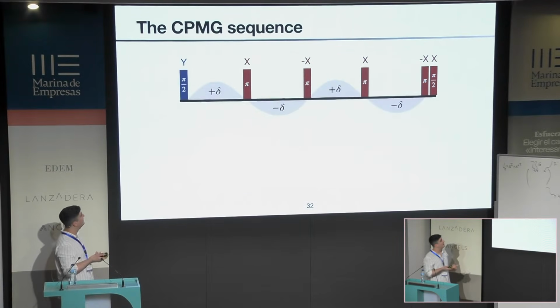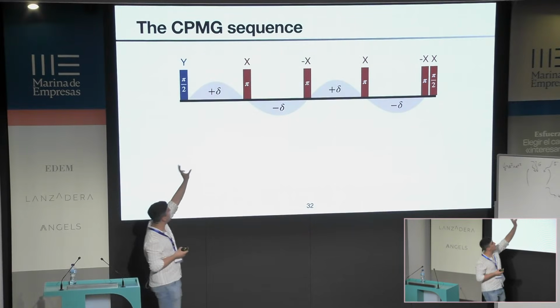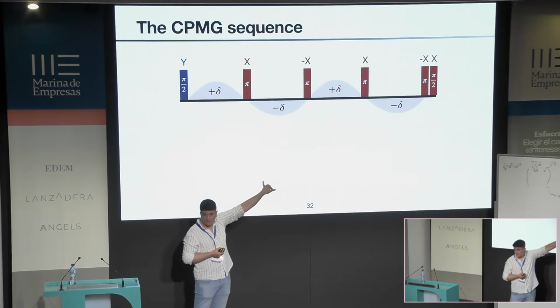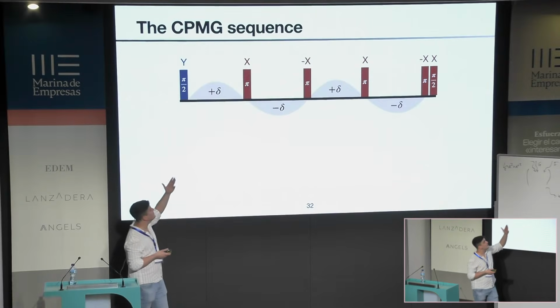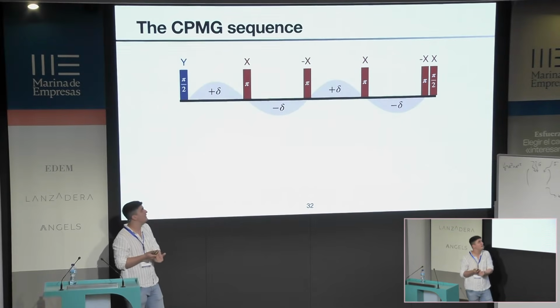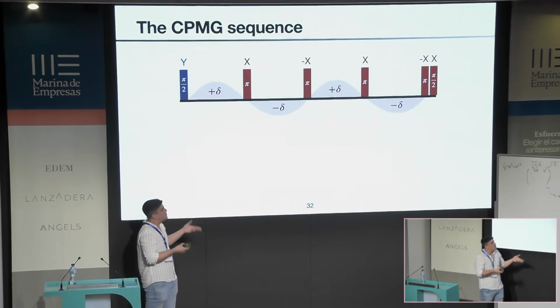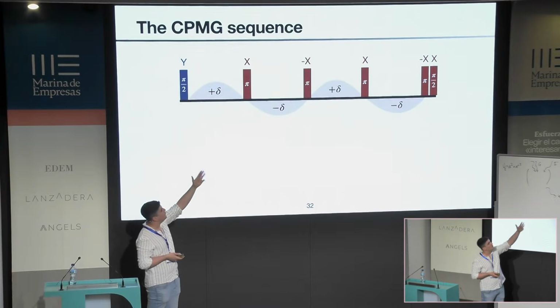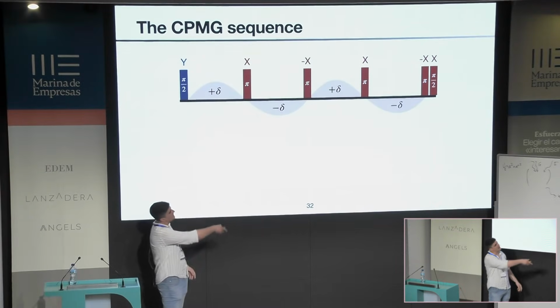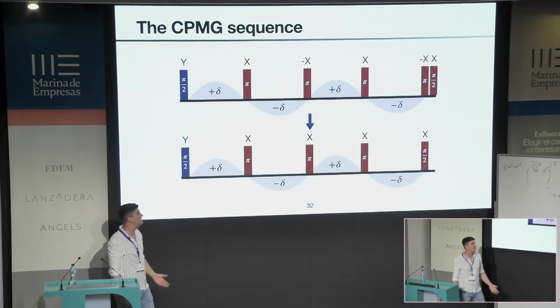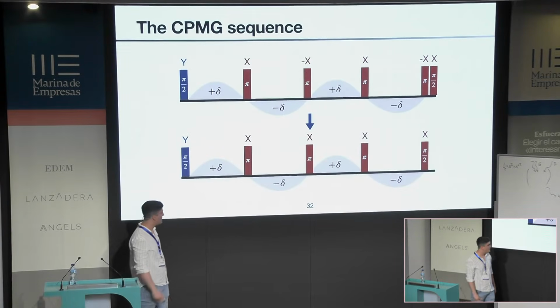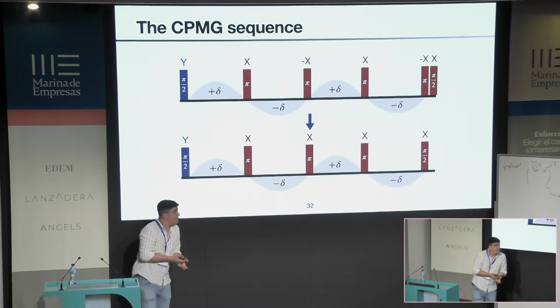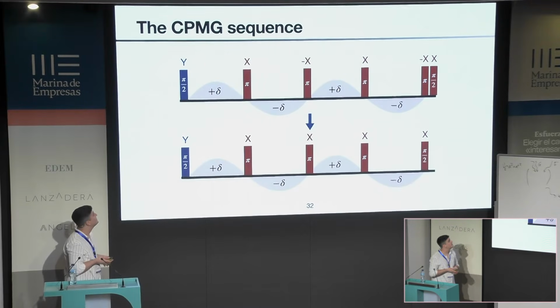And then we can extend it. Of course, we don't need to measure only one oscillation. We can measure more of them. This is now called the CPMG sequence. And in fact, we can simplify it. It's very easy to show, but the idea is the same, that we don't need to do -x, and we can spare the last pulses. And this is the form that everybody uses. Works exactly the same. And with this thing now, we can measure oscillating signals, finally.